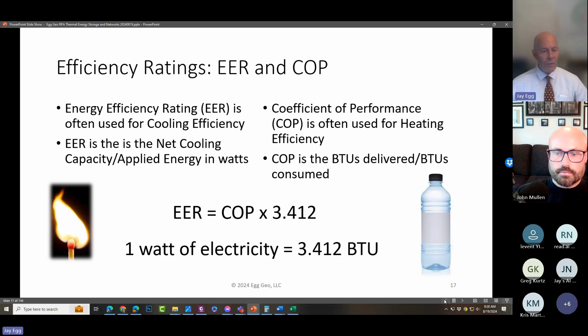If you're heating, we understand that we're trying to decarbonize the built environment because, as we understand, CO2 emissions are contributing to global warming. So we're trying to stop combustion of fossil fuels for the purpose of heating buildings. So if we go all electric, you'll see that you can use a space heater, which, with 1 kilowatt of electricity going into it, is going to deliver... That's why I gave you the conversion formula back here. 1 watt of electricity equals 3.412 BTUs. So 1 kilowatt of electricity going into a space heater is going to give you 3,412 BTUs per hour of heat. If you put that same kilowatt of energy into a heat pump, it's exactly that. It's a pump.